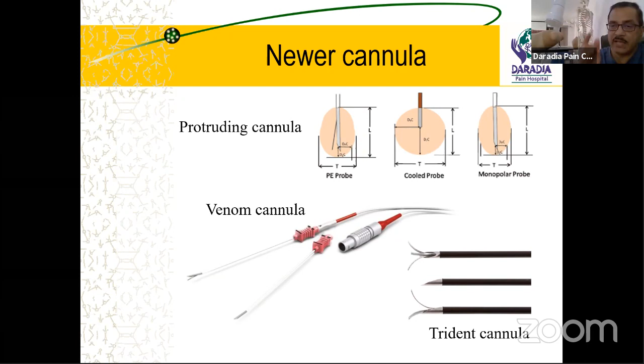If you are doing pulse radio frequency, we are having it on the tip, but the size is smaller. So this is for the conventional, this is for the cooled. Remember, the shape of the lesion between the conventional and the cooled: the cooled has a larger size lesion, and it is a spherical lesion, not a cylindrical lesion like the conventional one. And this is your protruding, and this is your bipolar. Bipolar means 2 conventional electrodes, and you are having a larger size lesion similar to the cooled radio frequency. But one disadvantage of the bipolar is you are not having any lesion beyond the tip. But with cooled radio frequency, beyond the tip you will have a significant size of lesion. That means even if your needle tip is a little bit away from your nerve, you can still catch the nerve.